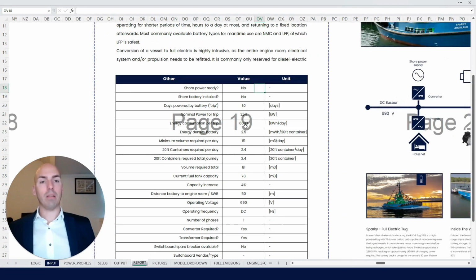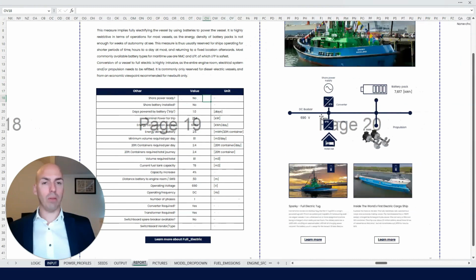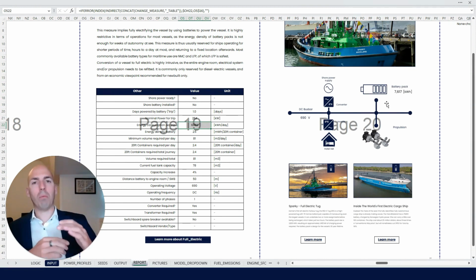That is the most important part, as we saw. So how come we have 7,000 kilowatt hours required per day, but a battery pack that's a lot bigger? Because you cannot fully deplete your battery pack. We've assumed at least 20% left over, and it charges up to 100%. So that's our state of charge high and state of charge low.